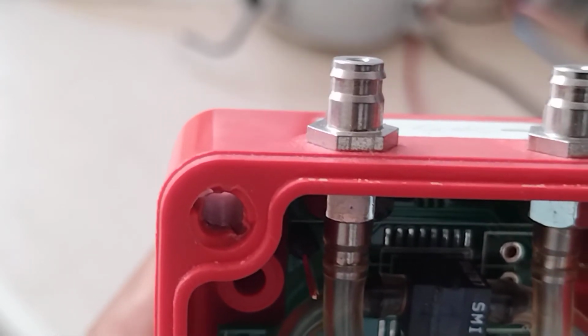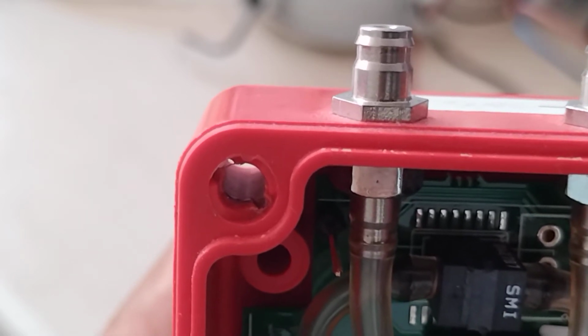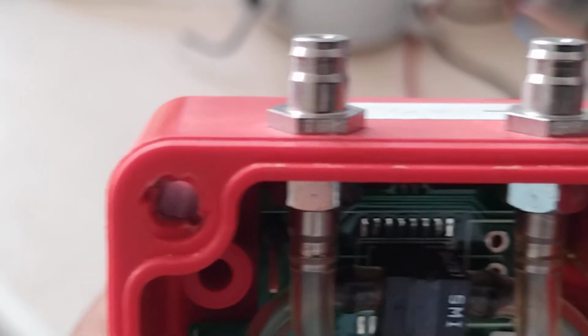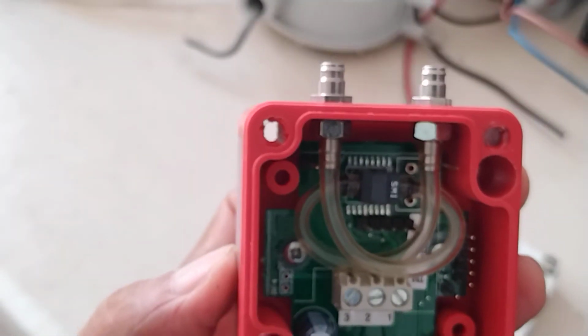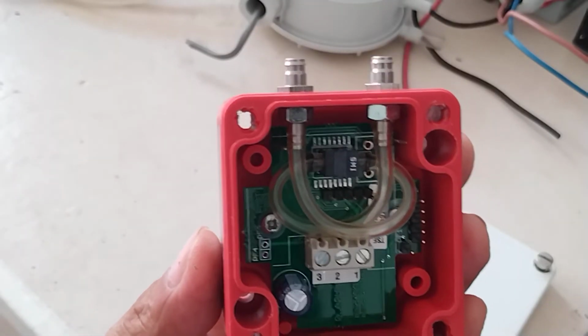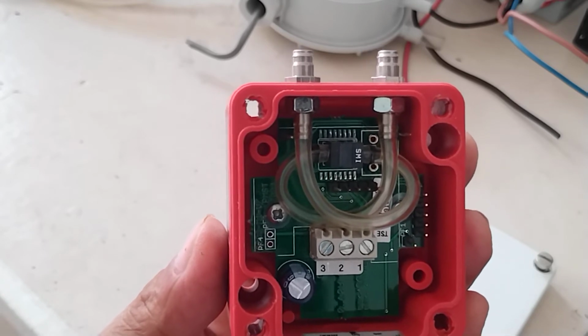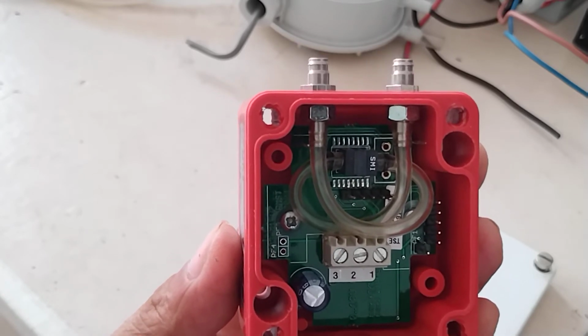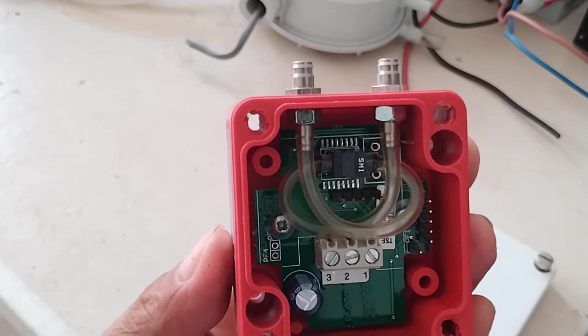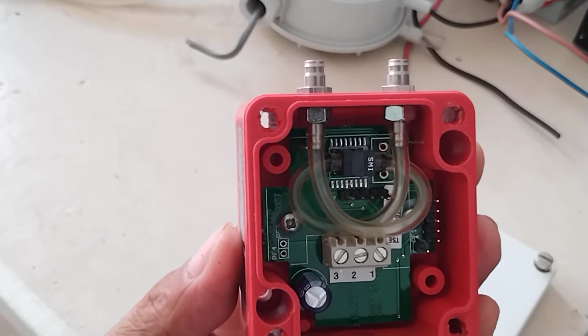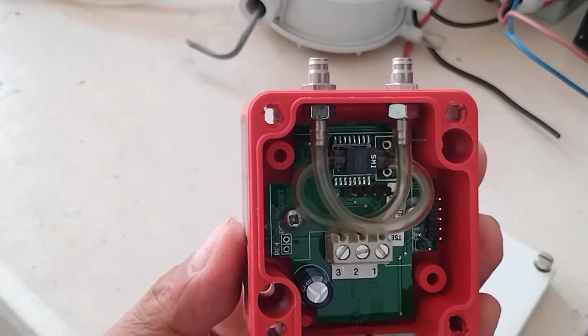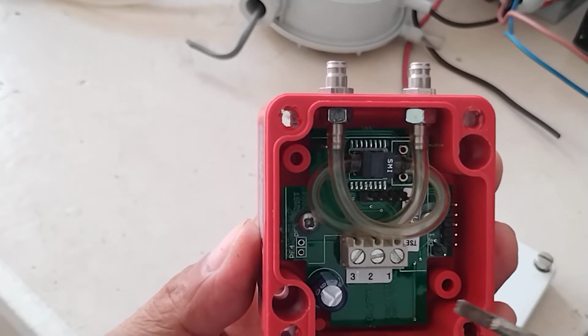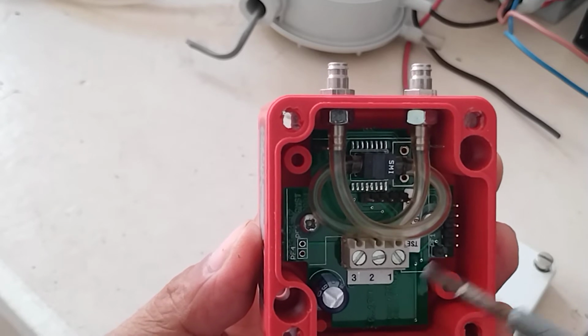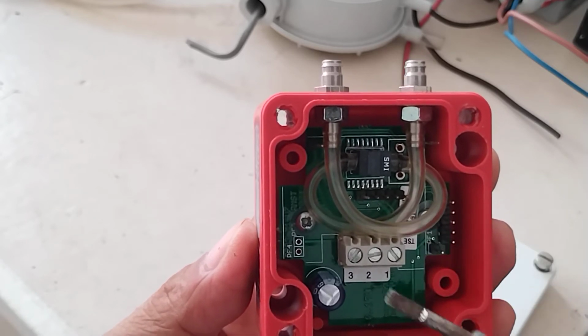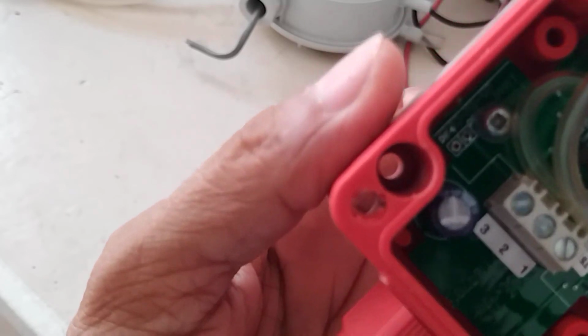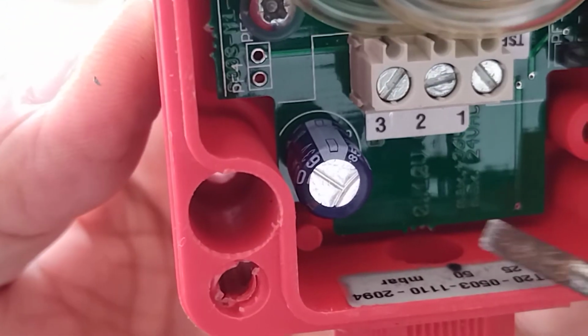So how are you going to install this in the equipment? Let's say you are trying to monitor the differential pressure across a fan. So how are you going to install this one? Actually, the installation is similar to the air differential pressure switch. But anyway, I will show you how you are going to install this one. But what is important here is how you are going to provide the power supply and how you are going to get the reading. Actually, the control output of this is 0 to 10 volts.